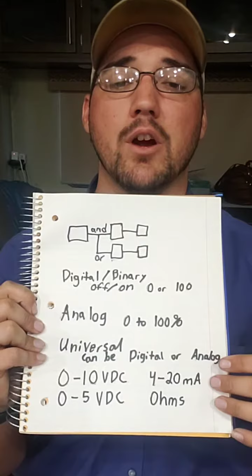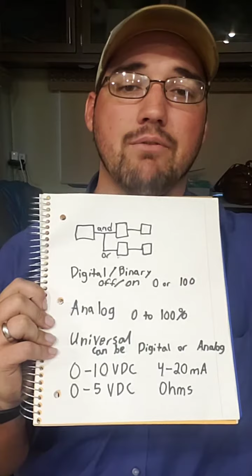Now, for those of you who don't know, the only way you are able to read a milliamp signal is to put your meter in series with the control circuit. Okay? You need to verify that your meter actually reads milliamps in the first place. A lot of your actuators could have a milliamp control system just as well as a 0 to 10 volt DC. So instead of sending 0 to 10 volts to that VFD or that actuator, to control it, it could be a 4 to 20 milliamp.